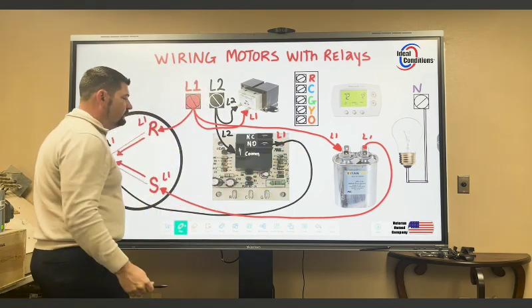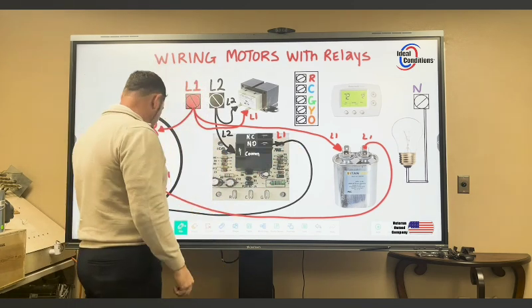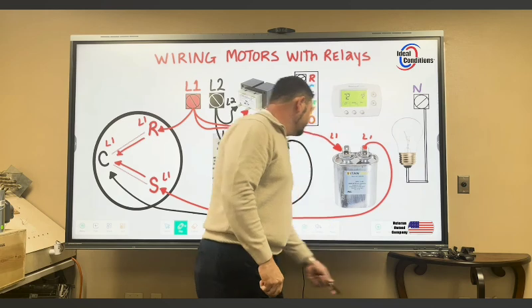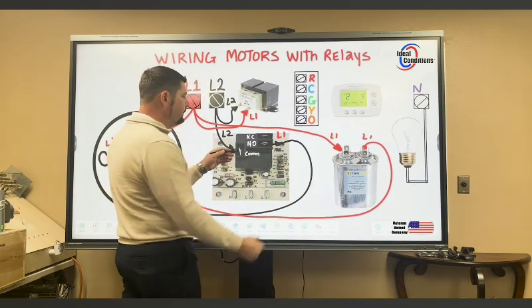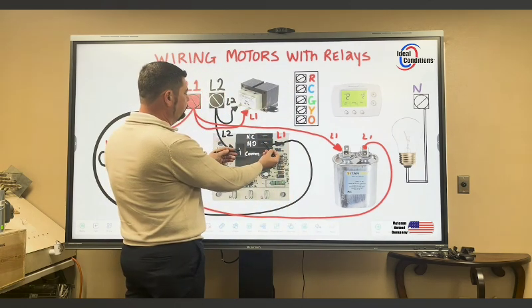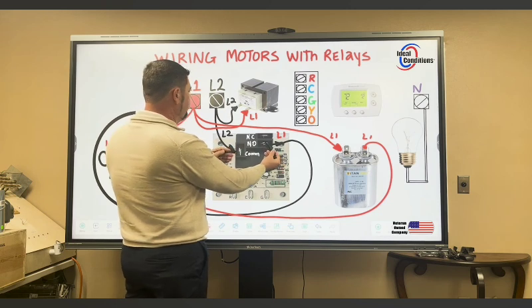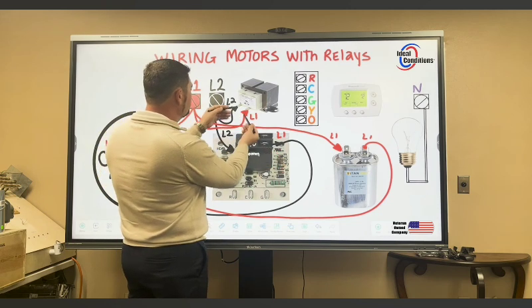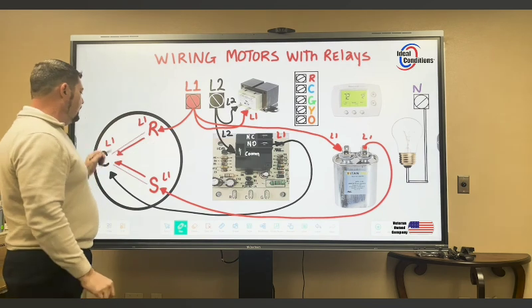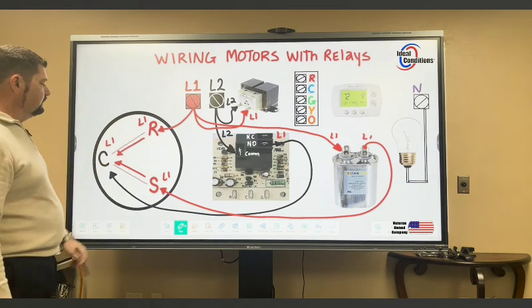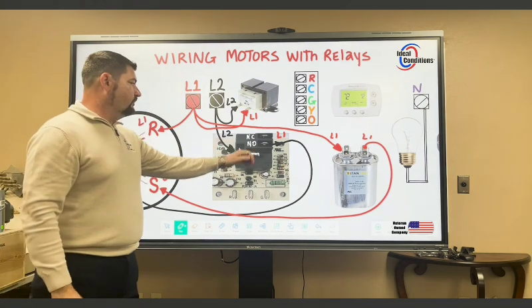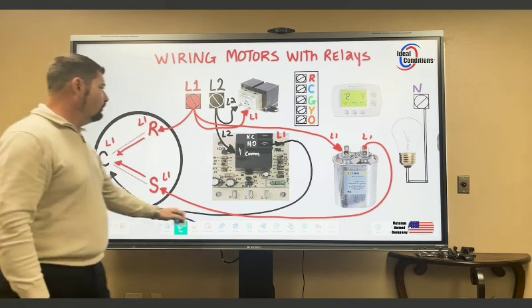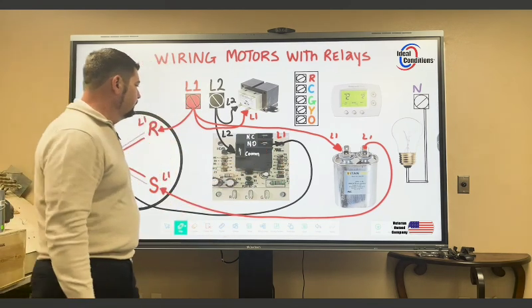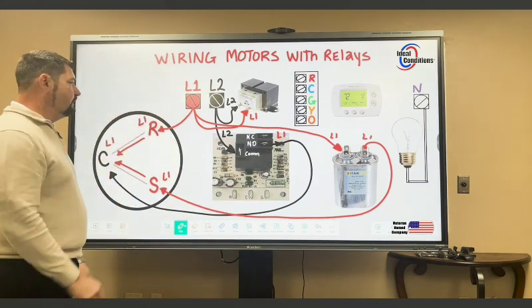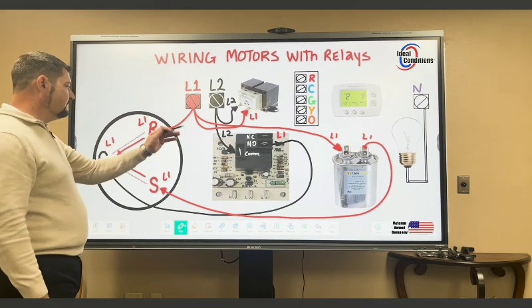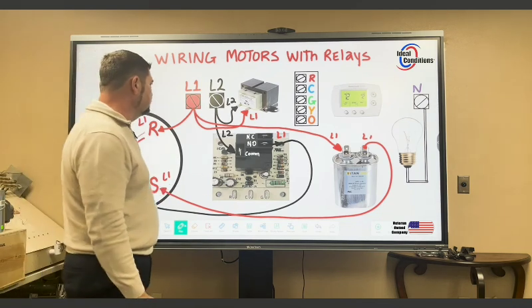Now the reason why, if I took my meter out and measured across this relay that's on the board between common and normally open, I'm going to read L2 plus L1, which is 240 volts, the same as I would read it here or here. There is no L1 plus L2 on the motor yet because L2 hasn't made it across. So the path of electricity puts L1 back here. So you've got to be careful, there's still power there. We're going to leave it like that until we wire the low voltage side.